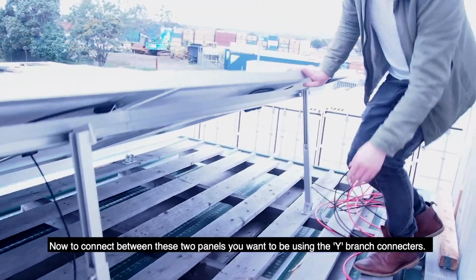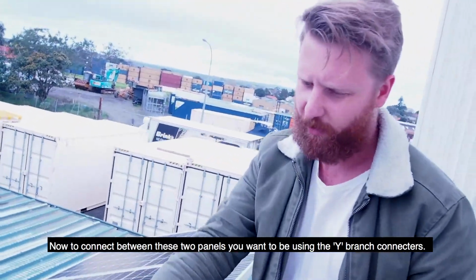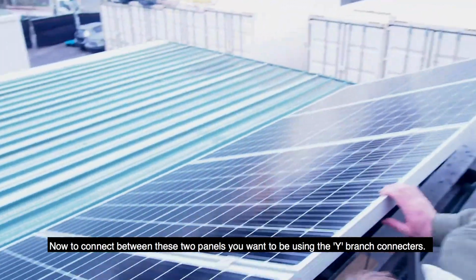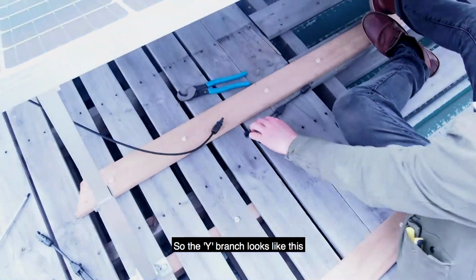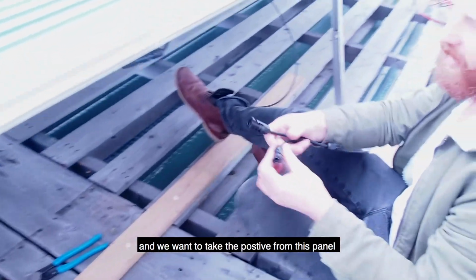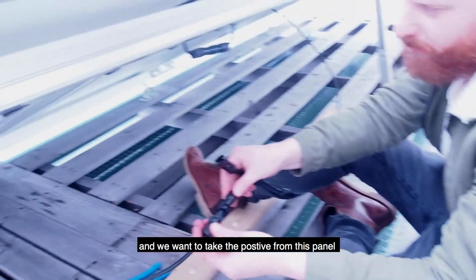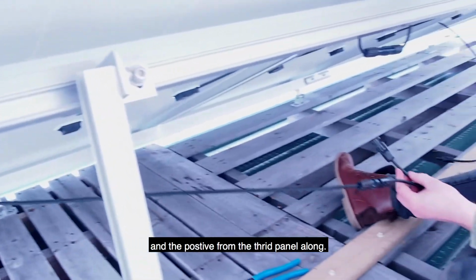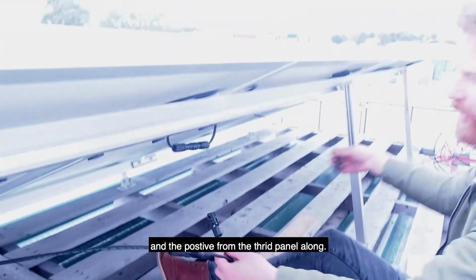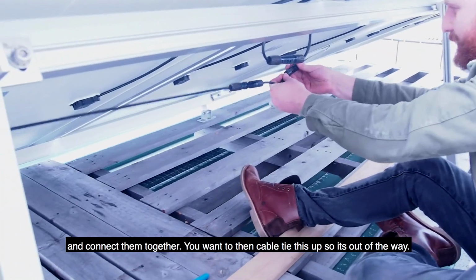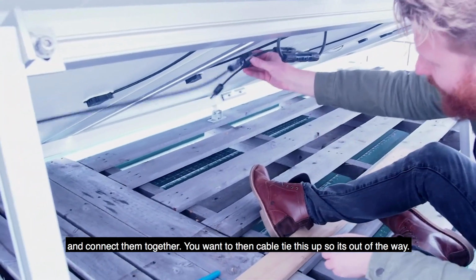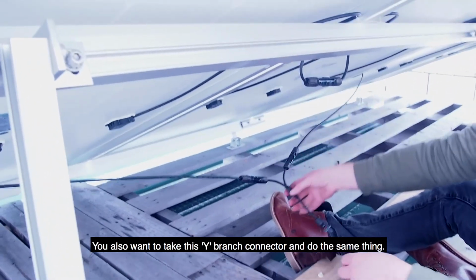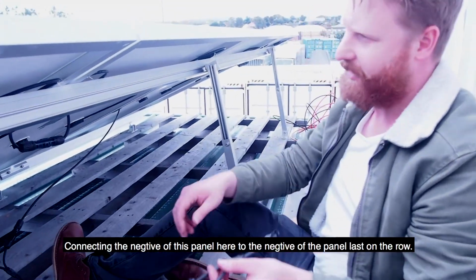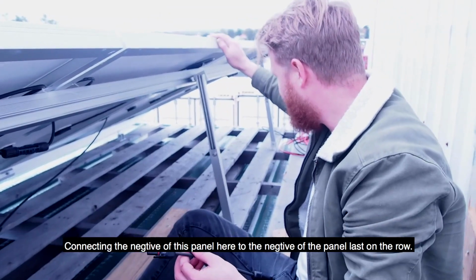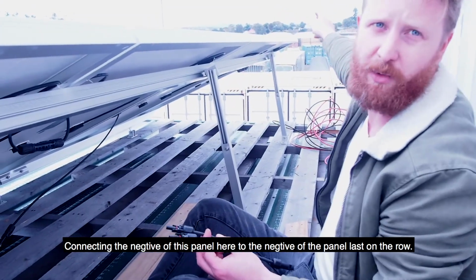To connect between these two panels, you want to use the Y branch connectors. The Y branch looks like this. Take the positive from this panel and the positive from the third panel along and connect them together, then cable tie this up so it's out of the way. Also take this Y branch connector and do the same thing, connecting the negative of this panel to the negative of the panel last on the row.